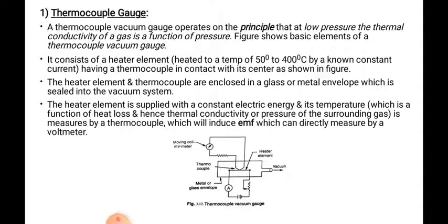By sending 1 bar, 2 bar, and 3 bar of air, we see the respective voltmeter readings, and by using that we mark the scale on the voltmeter, or it will already be there. So in that range, at 1 bar pressure the voltmeter will show 1 volt, and for 2 bar pressure the voltmeter will show 2 volts.